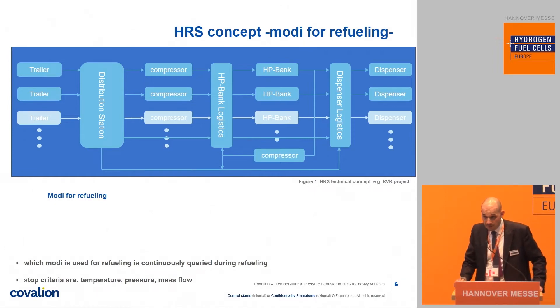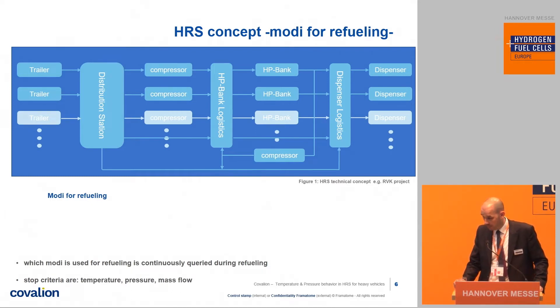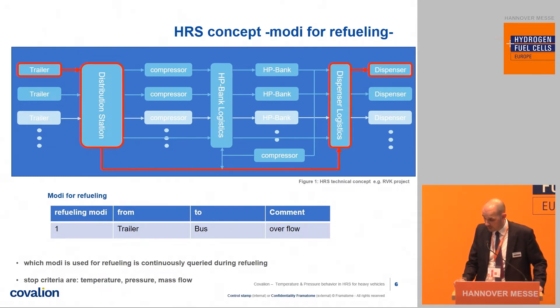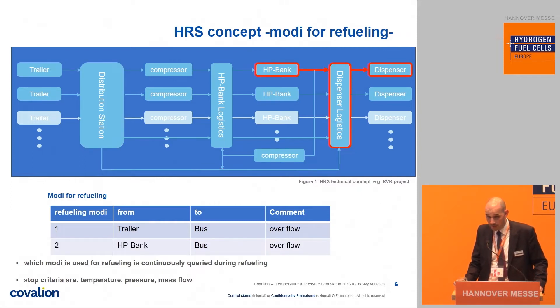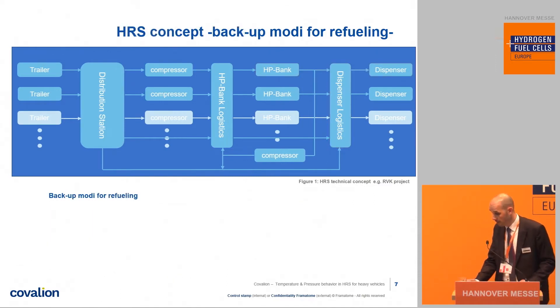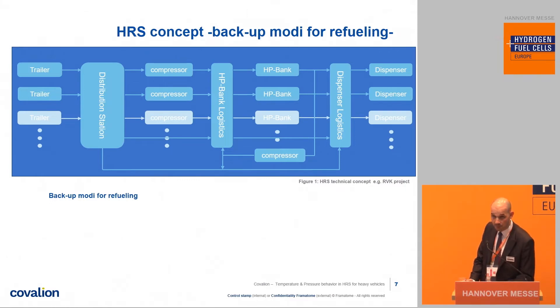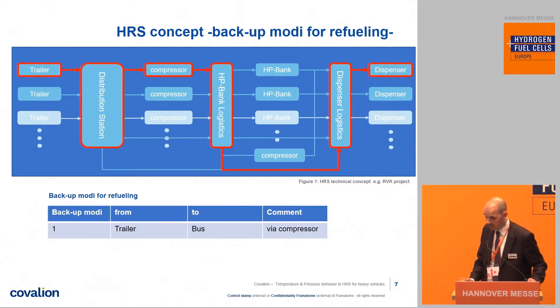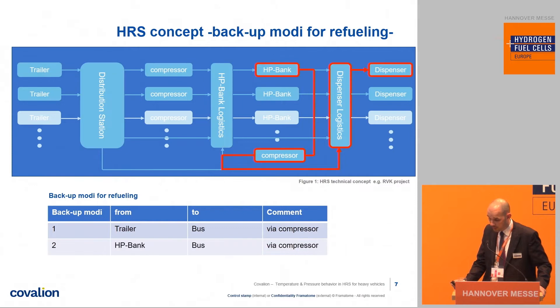We have different modes for the hydrogen refueling station concept. The first is the refueling mode. Here we can use two ways to refuel the bus: first, we can use hydrogen from the trailer to the bus via overflow; second, we can use our high-pressure vessels to refuel the bus via overflow. A second mode is the backup mode — for example, if the pressure is lower than needed for the overflow principle, we can use hydrogen from the trailer and the compressor unit to refill the bus.